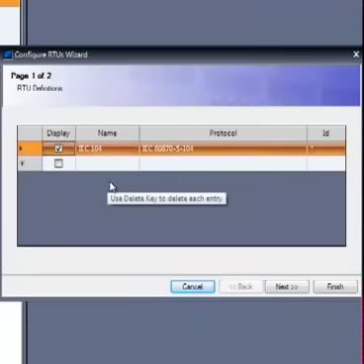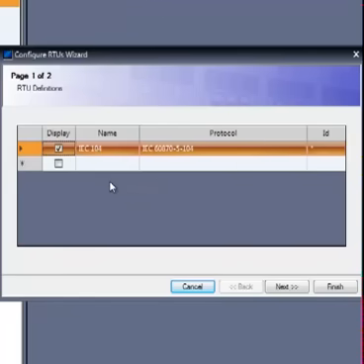For the family of IEC protocols, the RTU ID is typically the data link address. Since 104 protocol does not use a data link address, this field should remain unmodified.